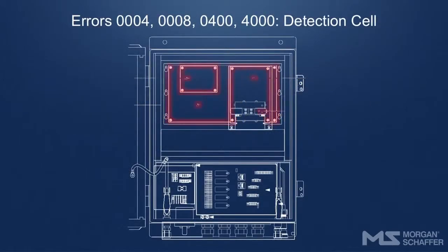Errors 0004, 0008, 0400, 4000, detection cell. Please contact Morgan Schaffer for assistance. 2 parts may need changing following a problem related to these errors: the main I/O or the gas detection cell.